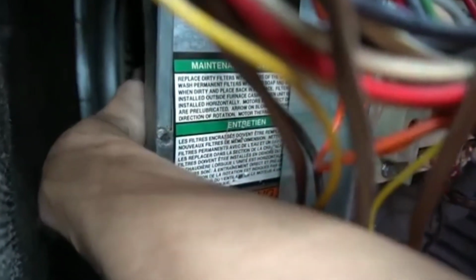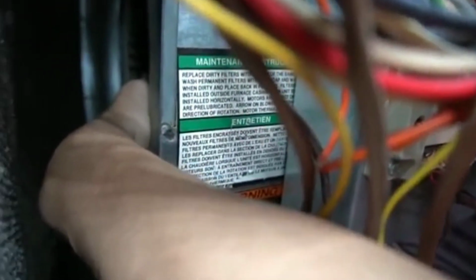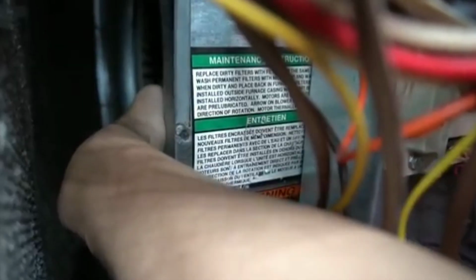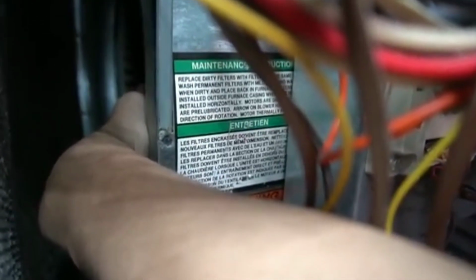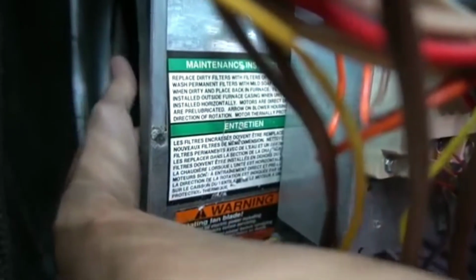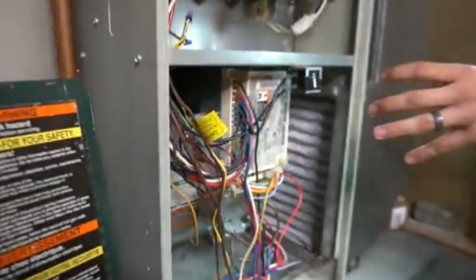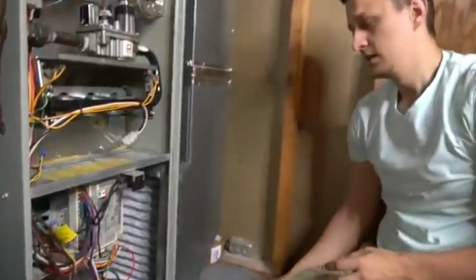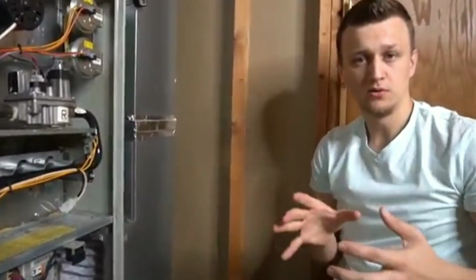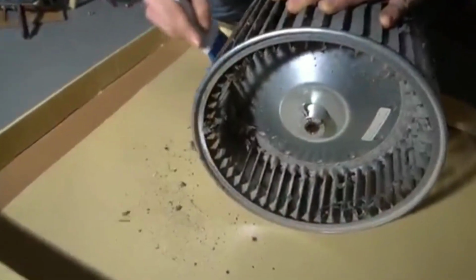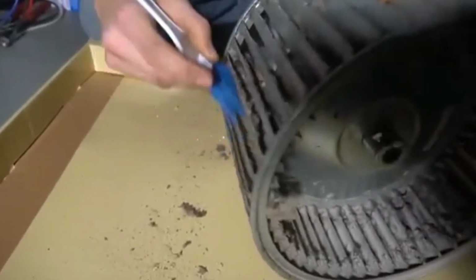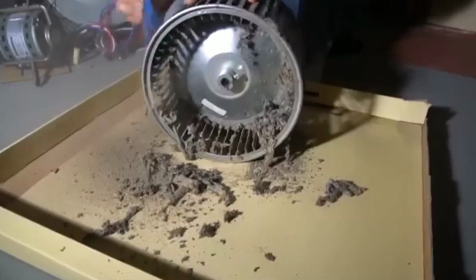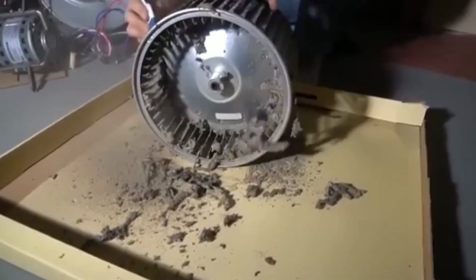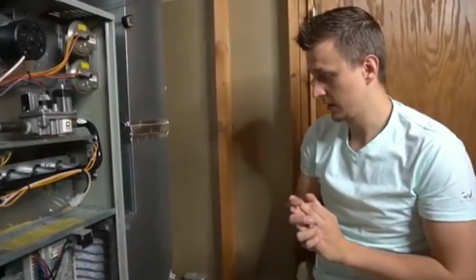If you feel a lot of dust in there, that means you may need to clean up that blower wheel, because that really restricts the airflow. If you have a lot of dust and other gunk in there, that really messes with the airflow. And I do have a video where I replaced my blower motor, and in that same video I took that blower wheel out and cleaned it up, and mine was really filthy. So if you want an example of a really dirty blower wheel, that one was mine, and in that video you see a bunch of gunk coming out. So if you want to see that, go ahead.